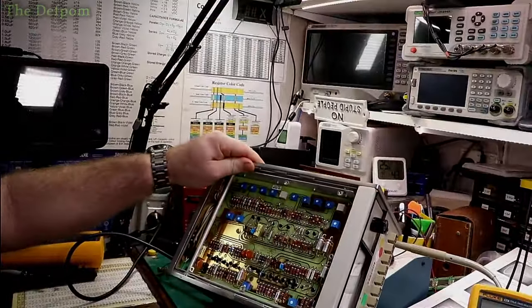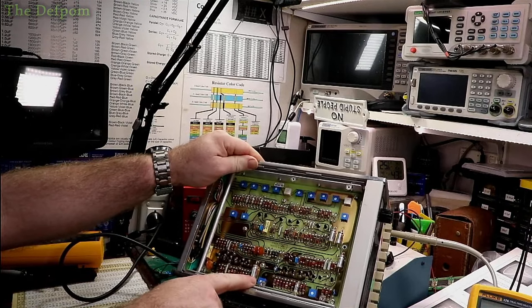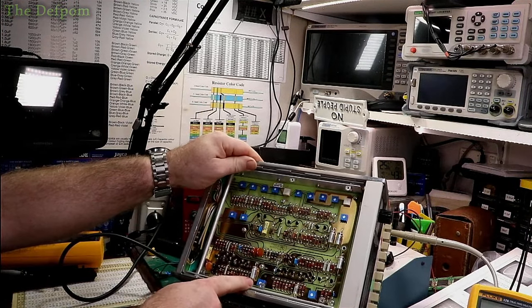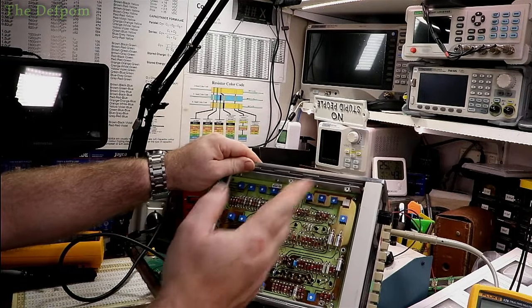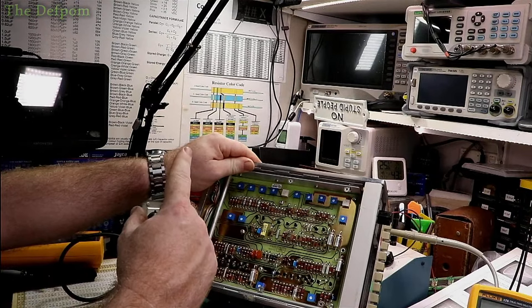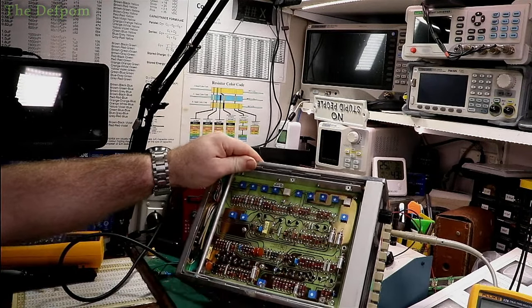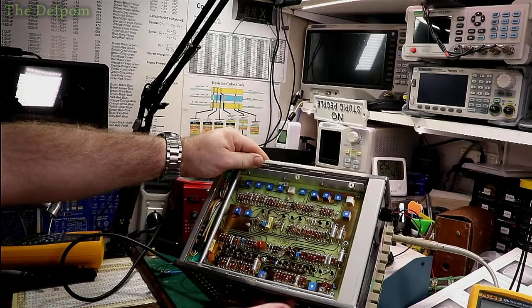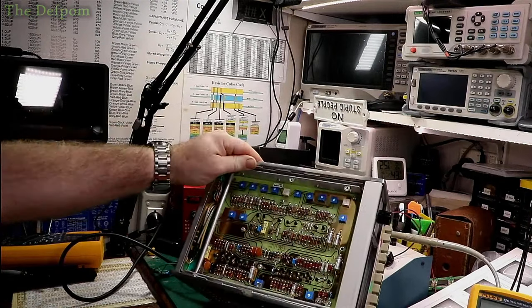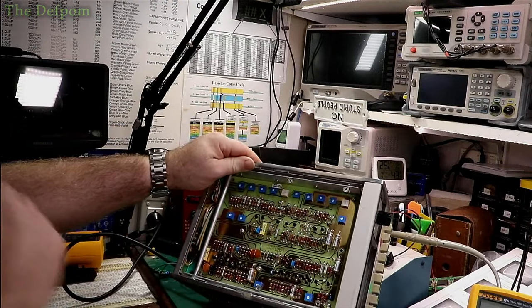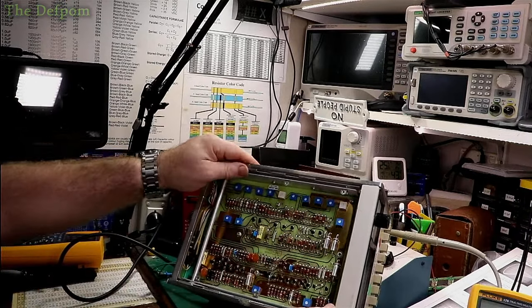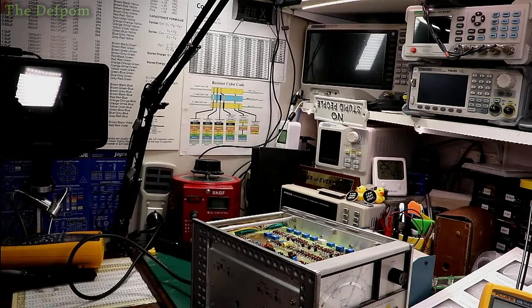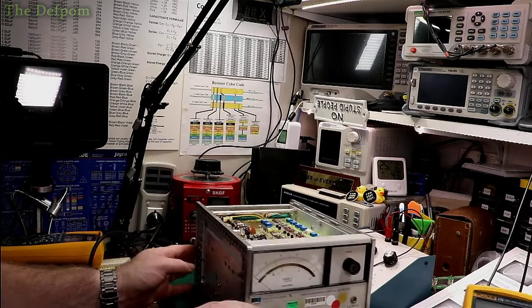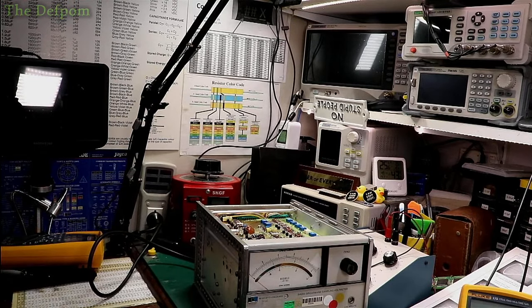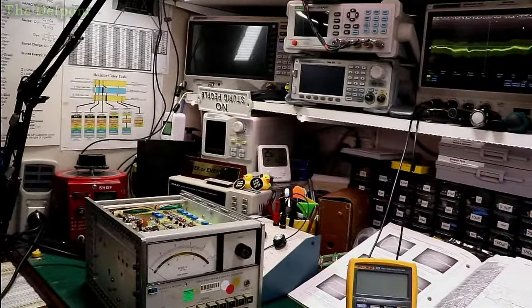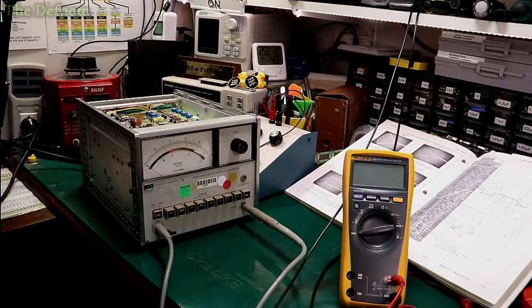On the top board, which you can't see, the only adjustment I've changed is this one here, that R19. But I did make a note of where it was pointing. I put it back in exactly the same place. And that is one of the ones that helped pull the needle right down at 0.03 volt range. So I turn that all the way down and then do the balance adjustment on there, wherever it was, there. And that would bring it down and get it so I could actually see a needle movement doing testing. But that was a bit of a bodge. But why is it working? I don't know. It's a mystery. I don't like outcomes like that. I much prefer to have an actual outcome where I know what I did to fix it. Right now, that's not the situation I'm in.